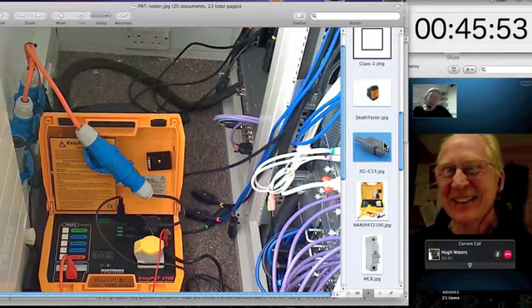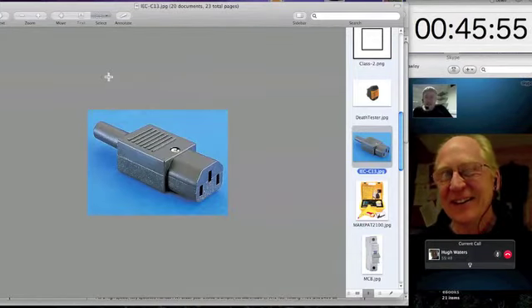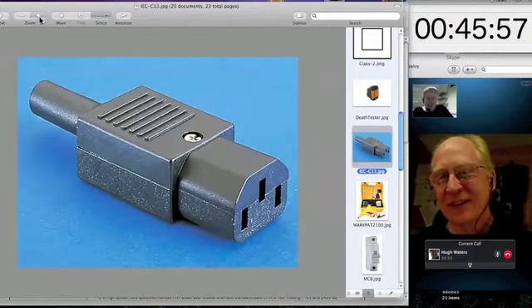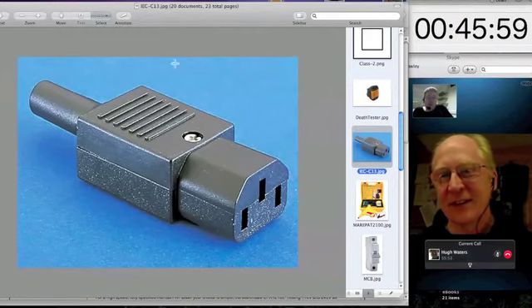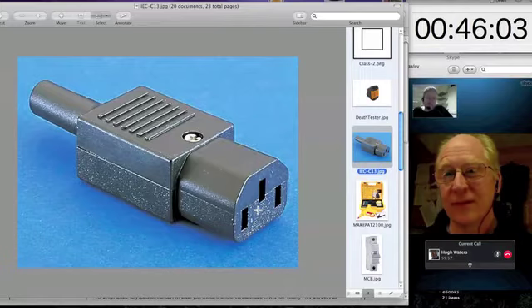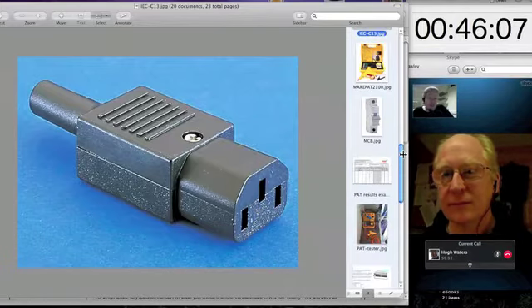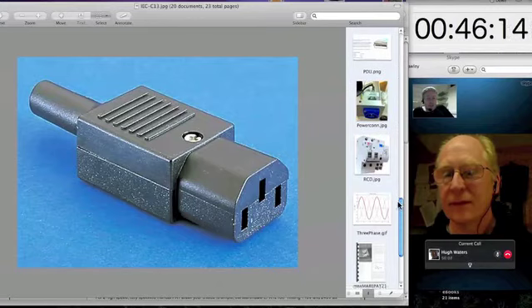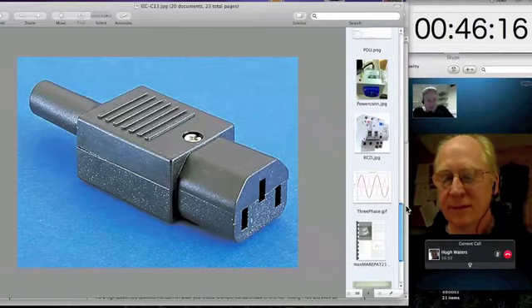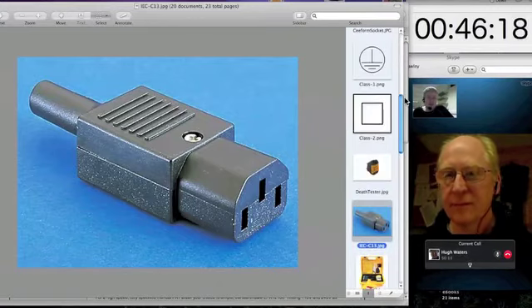And in the same way, I like to maintain segregation between domestic and technical power by using IEC type connectors, C13 connectors as they're called. Although increasingly equipment's starting to have what they call C19 connectors, which is a big 20 amp style connector on the back of it. So that's how I like to maintain the segregation between the two styles of supply.